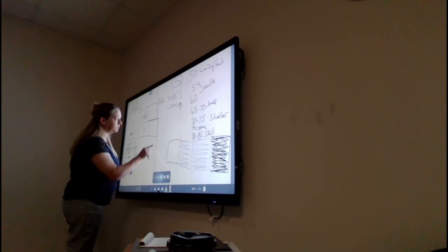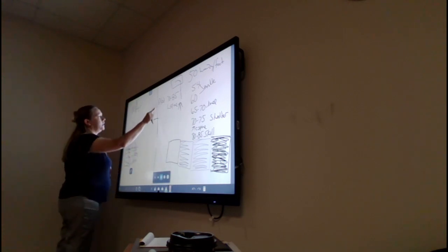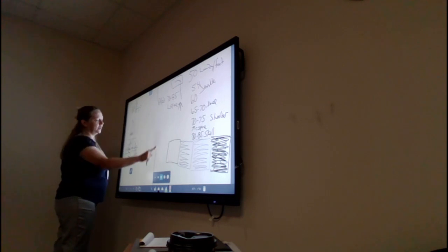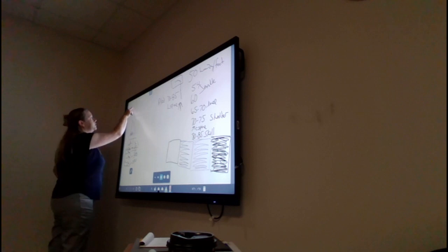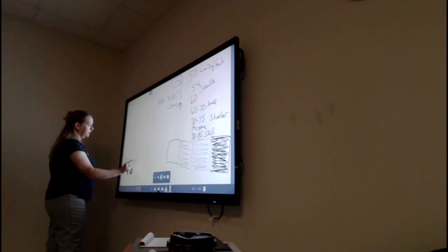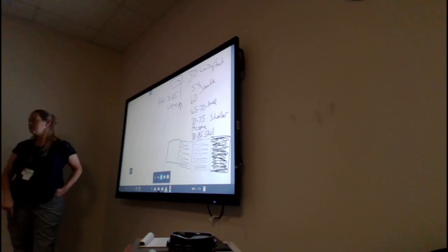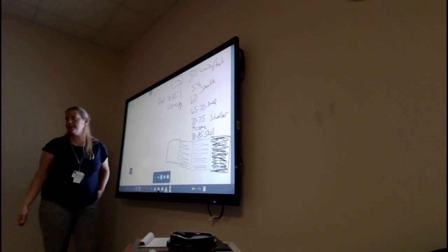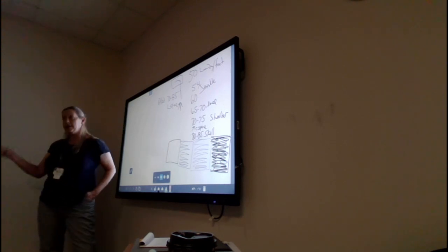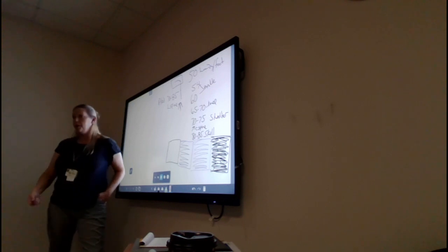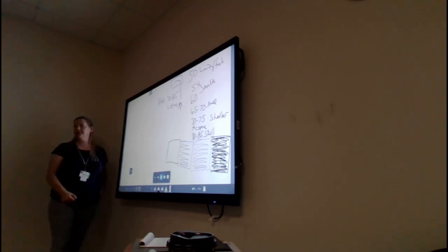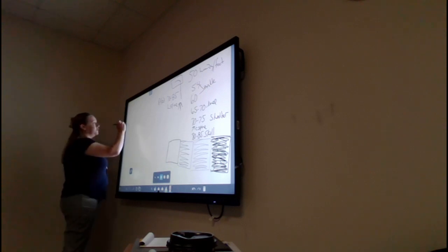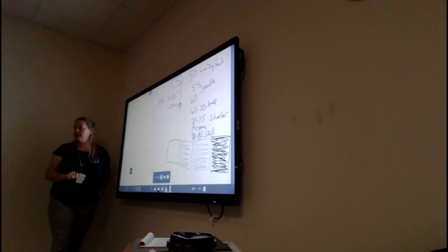The only thing that you can change on your machine is kVp or mAs. You see where I'm going with this? You don't have to know too much about, oh my gosh, 0.08 seconds plus XYZ equals this mAs. We have to know how to get there, and that's why I'm teaching you how to get there, but I could care less because here's the ultimate defining factor. I need you to be able to tell me what the mAs does.